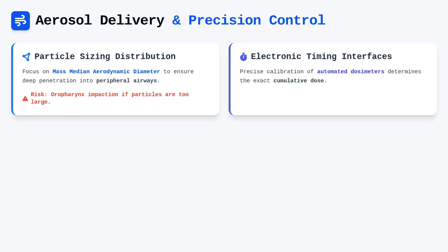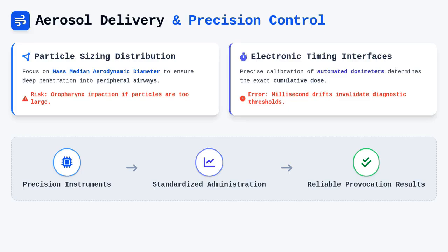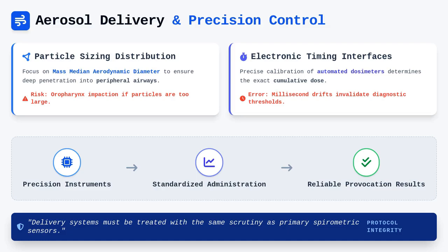Furthermore, the electronic timing interfaces for these automated dosimeters must be precisely calibrated, as the duration of the aerosol delivery directly dictates the cumulative dose received by the patient. If the timing interface is off by even a few hundred milliseconds, the consistency of the testing protocol is compromised, and the diagnostic threshold for a positive provocation result becomes unreliable. Achieving accurate results requires us to treat these delivery systems not as simple accessories, but as precision instruments that require the same level of scrutiny as our primary spirometric sensors.